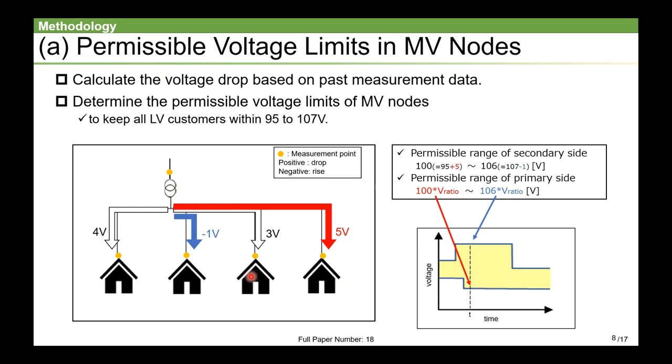This figure shows an example. When the voltage drop is like this, the voltage value on the secondary side must be within 100 to 106V, because this consumer needs to be at 107V and this consumer needs to be at 95V. Therefore, the permissible voltage of the primary side is equal to the secondary side voltage multiplied by the transformation ratio. In this way, the permissible range of the MV node can be determined based on every customer's voltage trend.